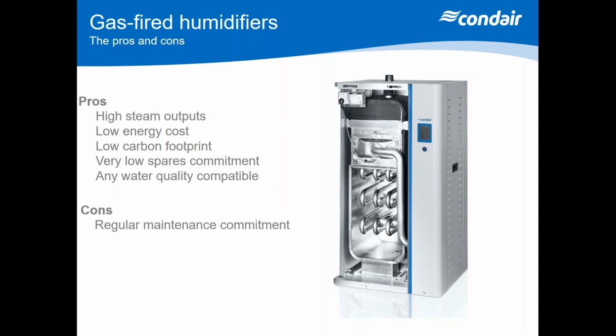But what you've got to consider with a gas unit is the gas supply to start with, the flue to run the CO2 or the combustion gases away, and also you've got to have ventilation in your plant room. So not every plant room can take them, and you're going to find that there are more requirements involved. Cost-wise, they are going to be a bit more expensive than resistive, but at the moment, as we say, gas is a little bit cheaper to run than electricity. That might change with renewable energy in the near future, but at the moment, gas is an option if you're looking at big duties. It's going to be a lower run cost.